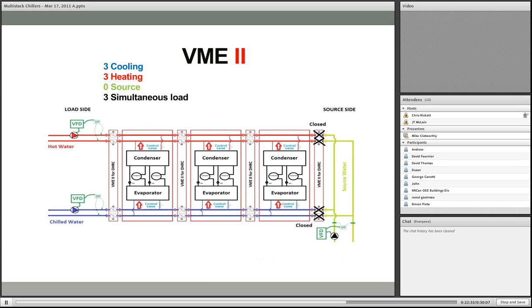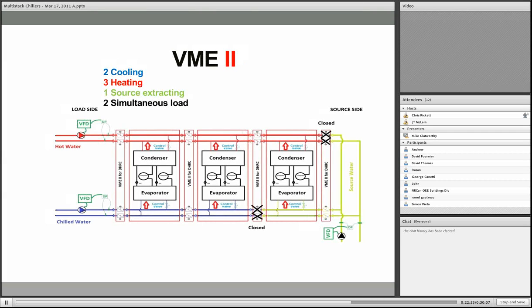Now, a typical commentary would be, does it have to be a geothermal well field? And the answer is it doesn't, but that's the most efficient choice. It could be a cooling tower, it could be fluid coolers or dry coolers, anything that you could use to get heat from the air or reject heat to the air or the earth could be used, but the most common choice and the most efficient choice would be to use a geothermal well field.